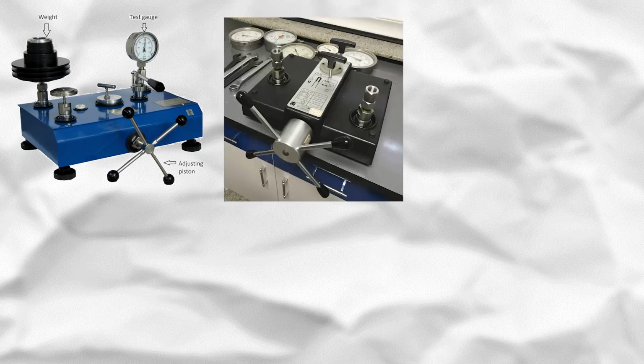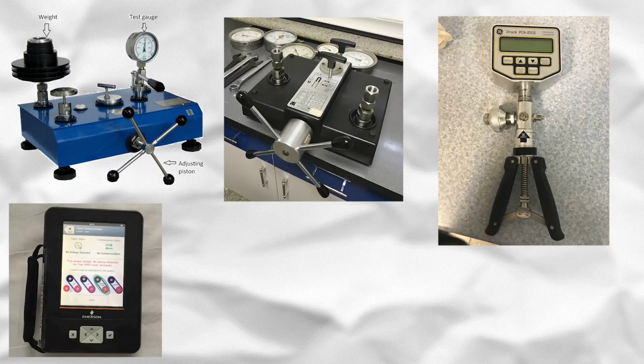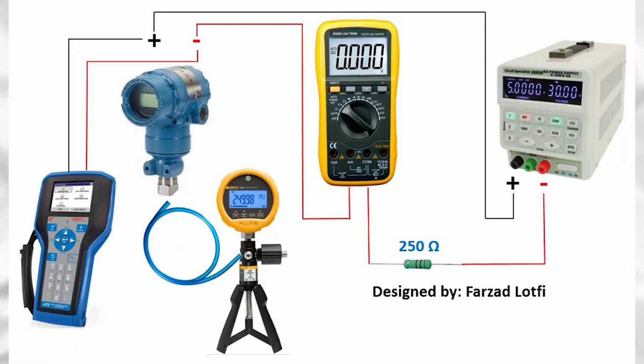To carry out the calibration procedure, not only do you need some reference calibrators, but also you must get familiar with the different kinds of errors. Deadweight testers, gauge comparator, hand pumps, HART communicator, milliampere source, and devices like them are widely used in calibration. The most well-known errors which may happen for an instrument are zero shift and span error. Before starting the calibration procedure, you need to prepare a table in which the points of calibration must be written. For instance, 0%, 25%, 50%, 75%, and 100% are written. Then you need to check the measuring amount in each point. After that, the difference between real and expected measuring amount specifies the action to take.